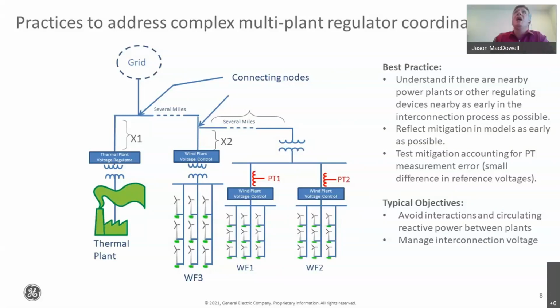That's a good question. Generally, short circuit ratio is based on the overall installed capacity of inverter-based resources relative to the amount of fault current provided by other, non-inverter-based resources. So to the degree that you can estimate the nameplate capacity of inverter-based resources to look at overall capability, yes, but you'll also need to understand the short circuit capacity from the balance of the grid to fundamentally understand grid stiffness in the area. So the answer is partially yes, as long as you can get a handle on the short circuit capacity from the balance of the grid without inverter-based resources.